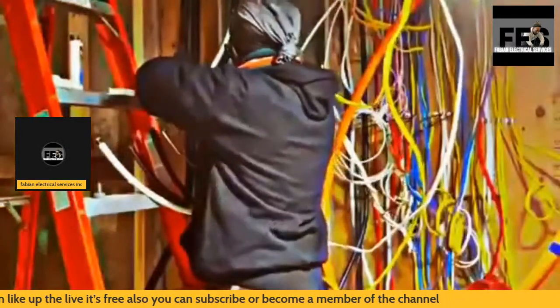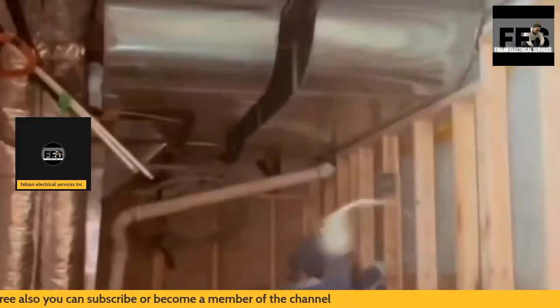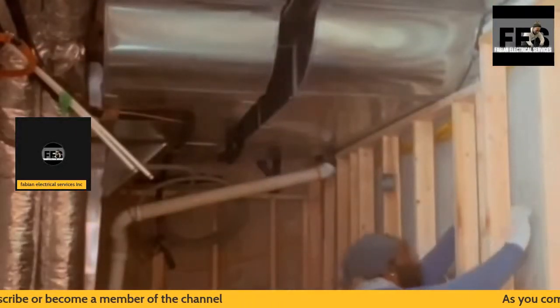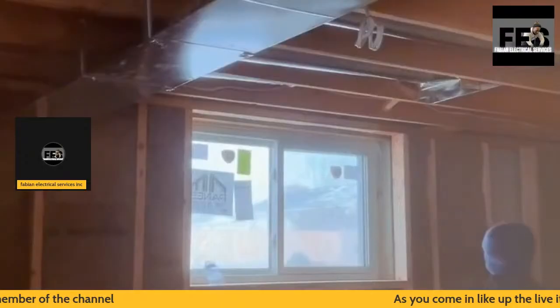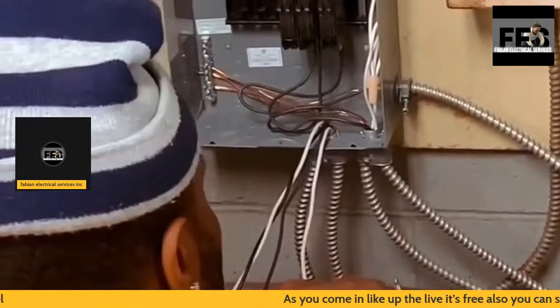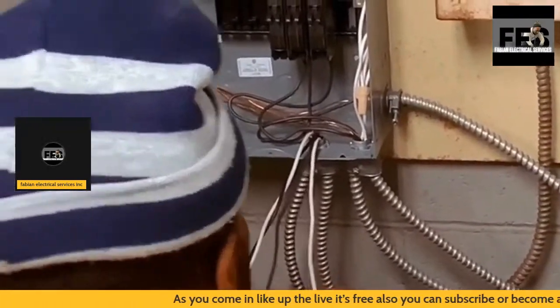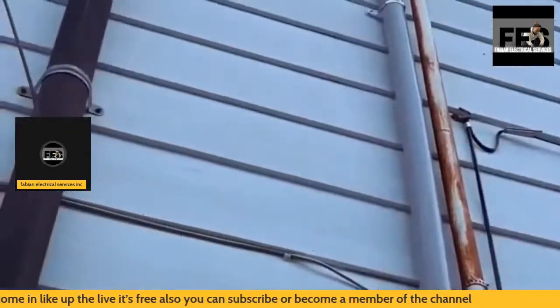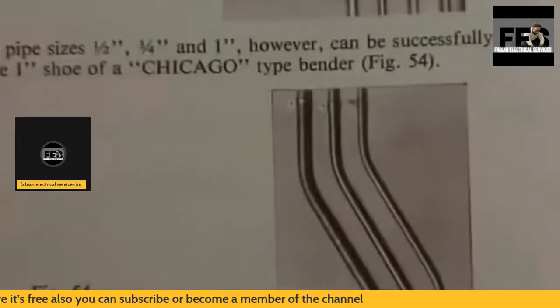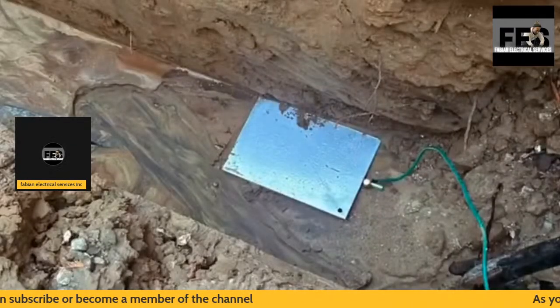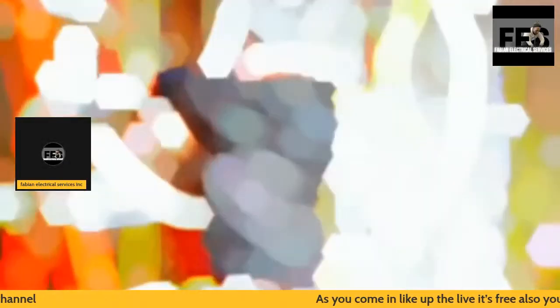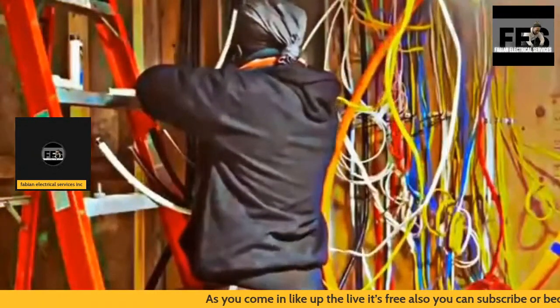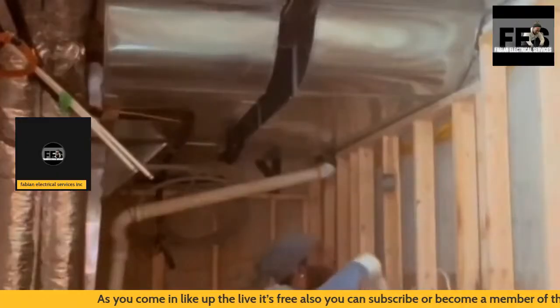When it comes to this installation, this is aluminum cable I'm using, so I have to protect my aluminum cable with noalox. It helps the circuit function a lot better when it's aluminum. We don't use it on copper, only on aluminum, and it's called anti-oxide. That's what we normally do with that type of installation.